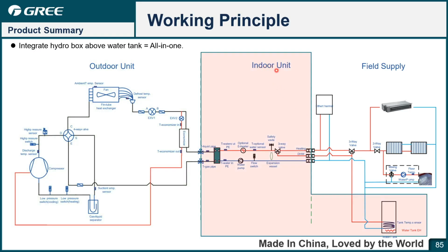If we put the indoor unit above the water tank and put them together, then you can get the all-in-one type. Yeah. So for the all-in-one type, these two water pipes are directly connected to the hydro box. So you just do the copper pipe connection and FCU floor heating connection. This part is saved, right? Is saved. So, okay, that's the difference between VERSATI 3 split type, monoblock type, and all-in-one type.